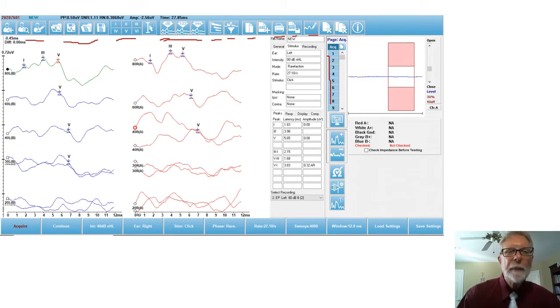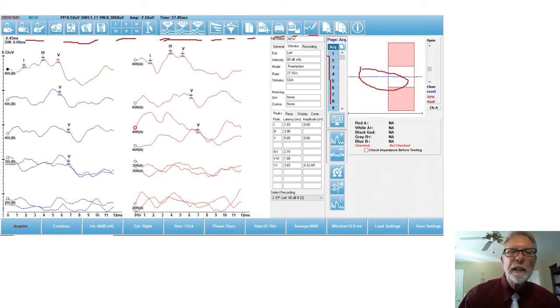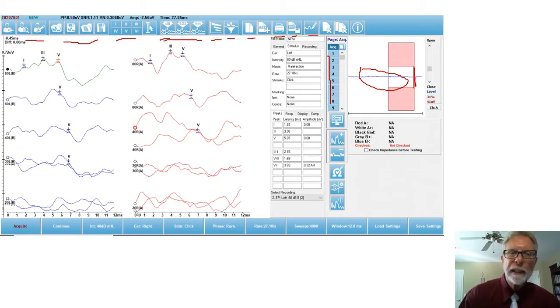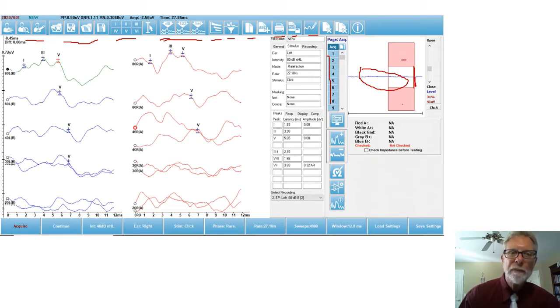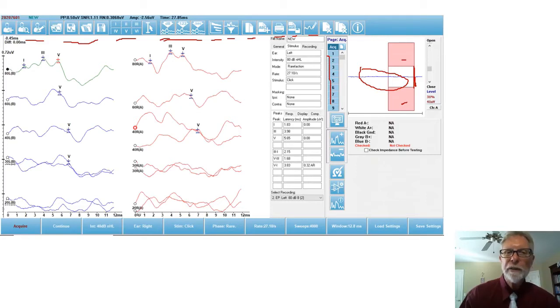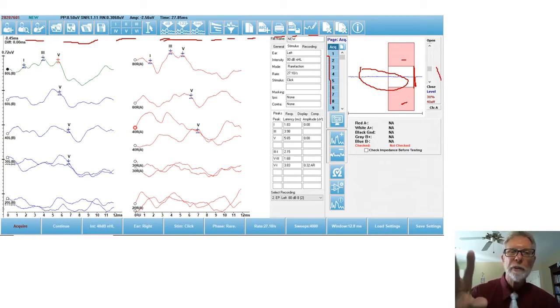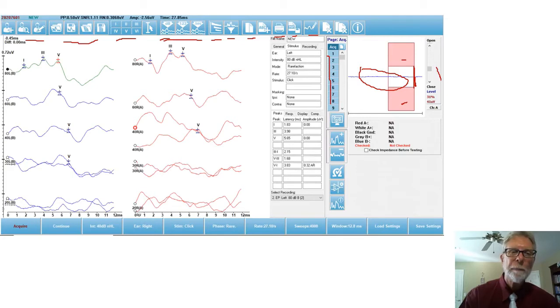And right here, you see the ongoing EEG, and this is the area that you can collect in as far as the amplitude of the EEG, and this red area above it and below it, of course, is the area that is rejected. And you can adjust that if you want. The adjustment's right over here. You can adjust that so that you can increase or decrease the artifact rejection level.